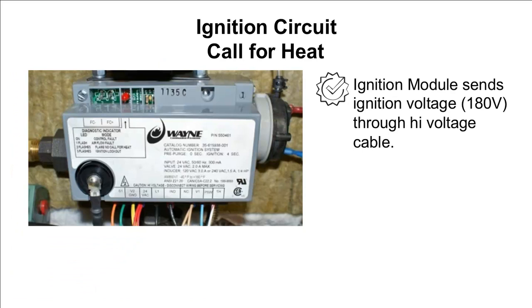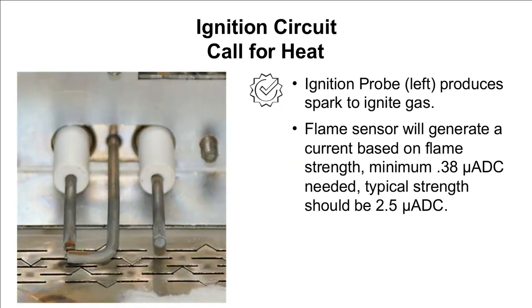Once the main valve has voltage, gas can now reach our burner. At the same time, the ignition module is going to send 180 volts through this high voltage cable right here to our igniter and attempt ignition. This is an inside look at the ignition probes, which is right here, and the grounding rod, which is here. We're looking for a spark around here. Obviously, we've got gas coming through our burner.